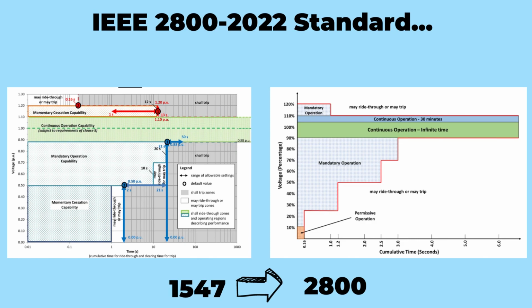Get ready to witness a groundbreaking transformation. The fault ride-through curve in the IEEE 1547 standard for distributed energy resources, DER, and the curve in the IEEE 2800 standard for inverter-based resources are poles apart, my friends. Brace yourselves for an electrifying revelation. In the awe-inspiring realm of the IEEE 2800 standard, a wider range of mandatory operation emerges, pushing the boundaries of what IBRs can achieve. This means they have the capability to handle a broader spectrum of challenges, empowering them to navigate through even the most demanding conditions with unparalleled grace and finesse.